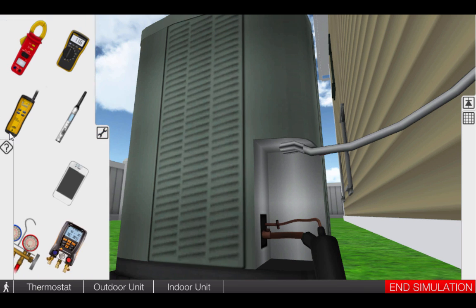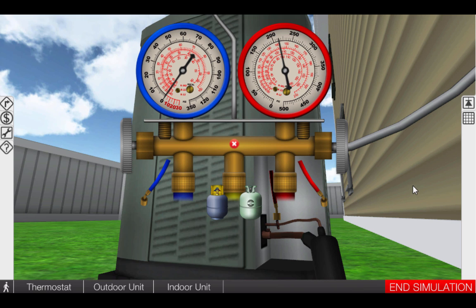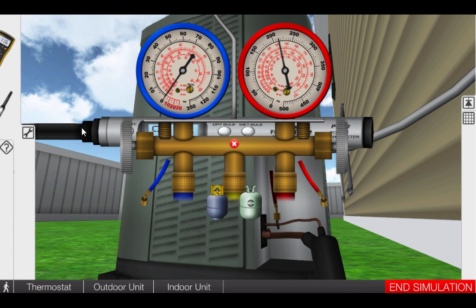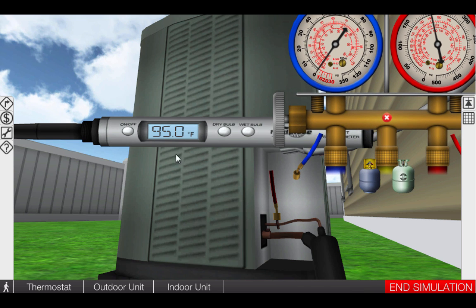Begin by taking the gauge manifold out of the toolbox. Place the red hose on the high pressure liquid line connection. We can see we have approximately 212 PSIG. The high side pressure should correspond to a temperature approximately 20 degrees above the outdoor temperature. If we take out the outdoor thermometer, we can see that it's 95 degrees outside. This means that under normal operating conditions, the refrigerant should be condensing in the condenser at approximately 115 degrees.